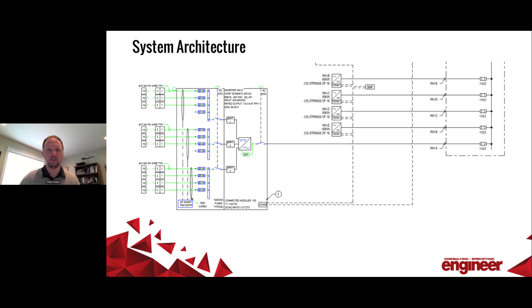Then I'll start paralleling those into the inverter. So in this example here, again, I have 10 strings connected to this inverter, all in parallel. They're broken into 3 groups, which connect to what's called a multiple power point tracking zone. For the sake of this conversation, keeping it simple, those are basically optimizing the power of the strings that are coming in from the solar there. So the energy produced by the PV modules, they're kind of a dumb device, and they need to be optimized to maximize the amount of power being pulled out of them. So the different MPPT zones here will allow for different orientations. This one here has 3 zones in it. So that might allow for 3 different orientations of the modules, or allow for shade tolerance. The microinverters I showed earlier would do that optimization at the module level.